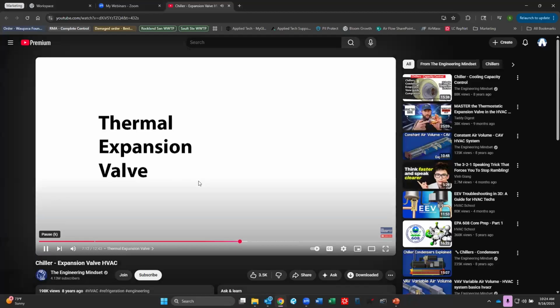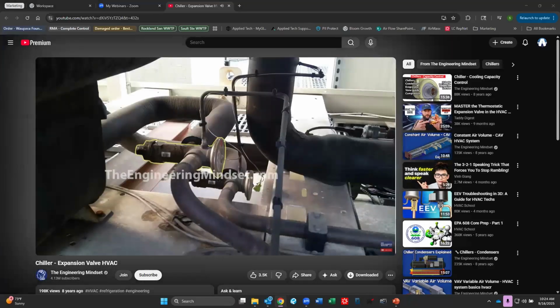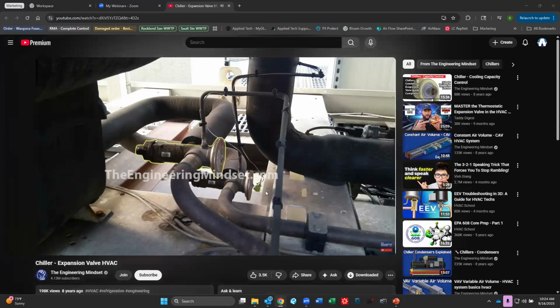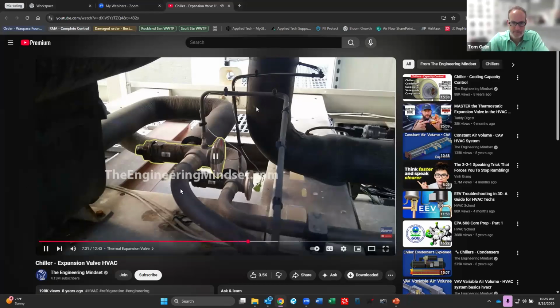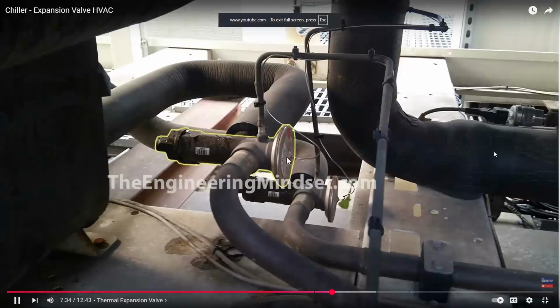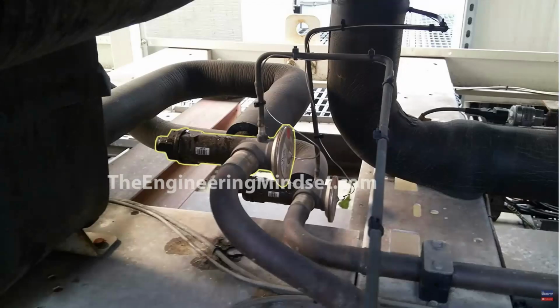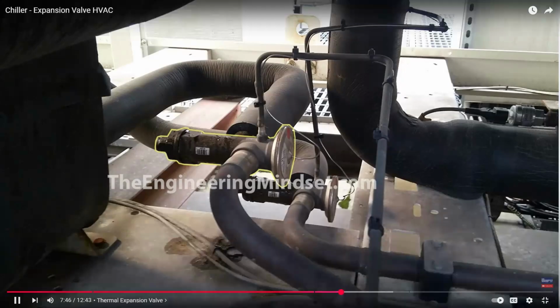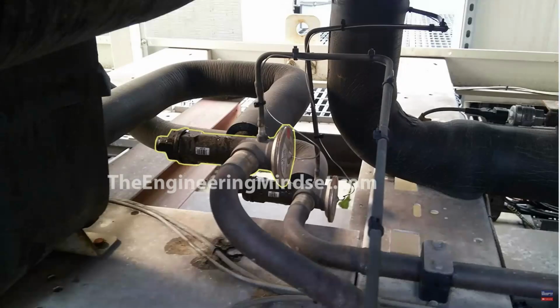Expansion valve we're going to look at is the thermal expansion valve. In the real world, the thermal expansion valve looks something just like this. So this one is actually on an air-cooled chiller, but it's still got the flow of refrigerant coming through and then going off into the evaporator. Can you go to full screen, the equalizer valve coming through there. And attached to the top of the thermal valve is the capillary tube, which goes off and measures the superheat. Now, these type of valves are usually found on smaller chillers.